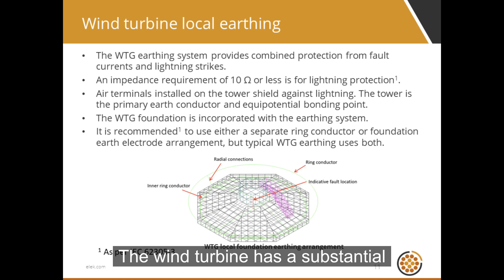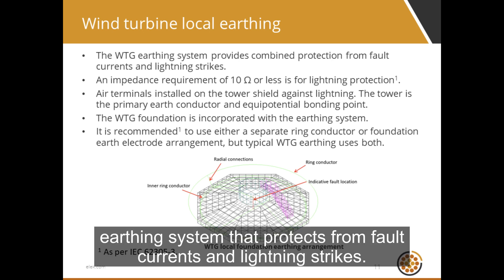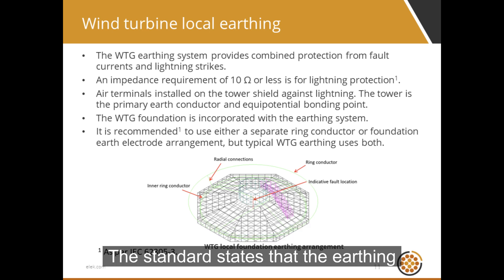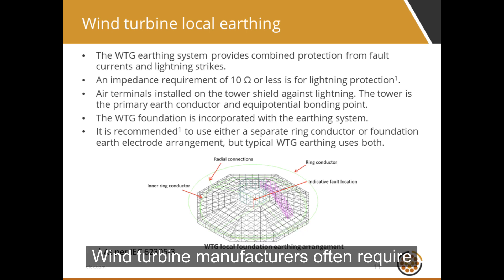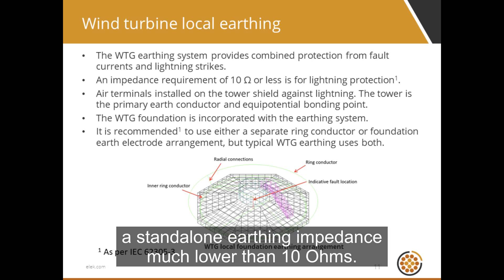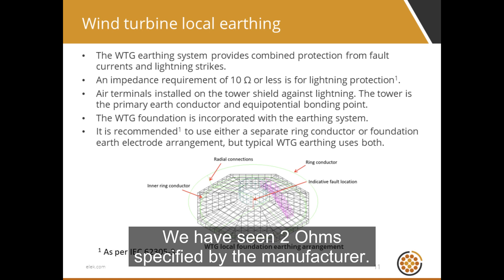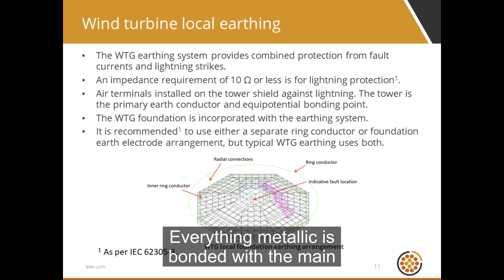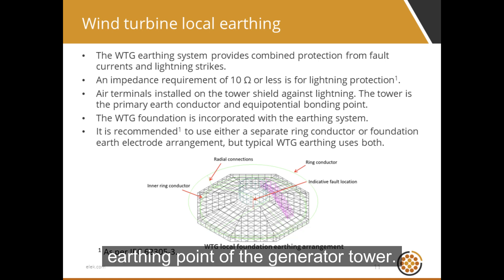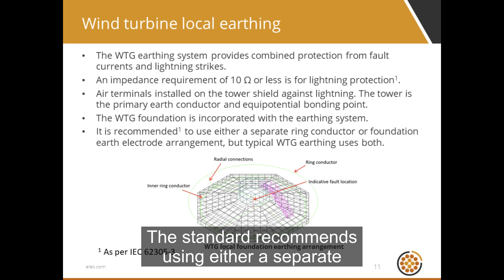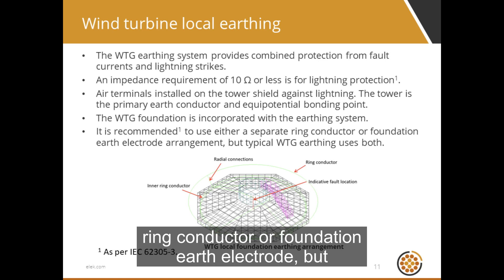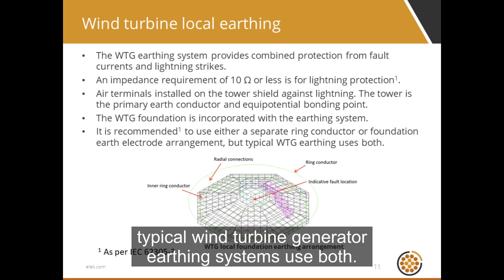The wind turbine has a substantial earthing system that protects from fault currents and lightning strikes. The standard states that the earthing impedance should be less than 10 ohms, measured at low frequencies. Wind turbine manufacturers often require a standalone earthing impedance much lower than 10 ohms — we have seen 2 ohms specified by the manufacturer. Everything metallic is bonded with the main earthing point of the generator tower. The wind turbine foundation is incorporated with the earthing system. The standard recommends using either a separate ring conductor or foundation earth electrode, but typical wind turbine generator earthing systems use both.